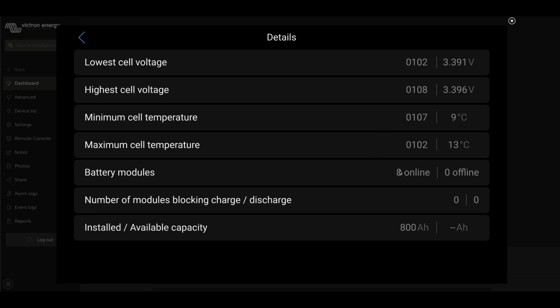In this particular bank, there are 8 batteries. All of them are online. None of them are doing anything to block charge or discharge. If a battery is full or if a battery is too cold, you may see one or more of them blocking charge and discharge. The cool thing here is that one of these batteries can block charge or discharge, and the whole system will continue operating. Installed available capacity, pretty basic numbers there.